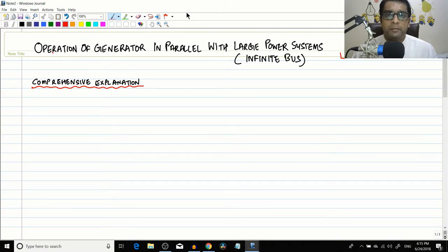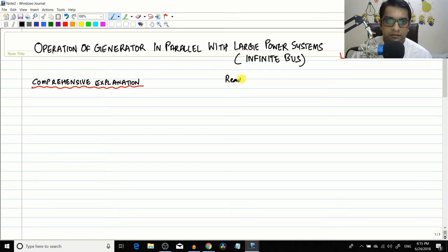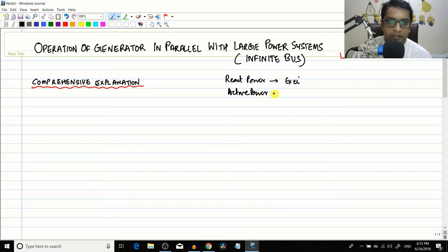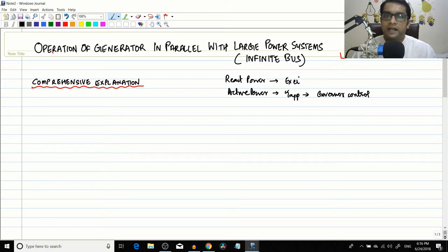In the previous couple of sessions we went through the topic of operation of a generator in parallel with large power systems. The conclusions were that reactive power supplied is controlled by excitation, and active power control is done by adjusting the torque applied, which is achieved by governor control. A simple way to remember these things was also presented using a mafia example — if you haven't seen that video, check it out.